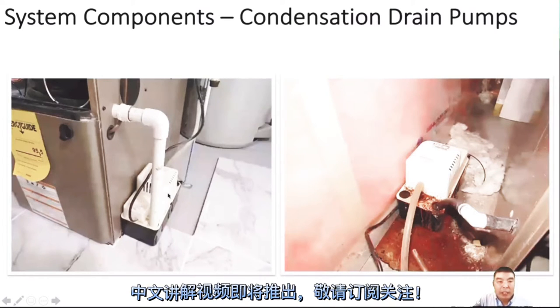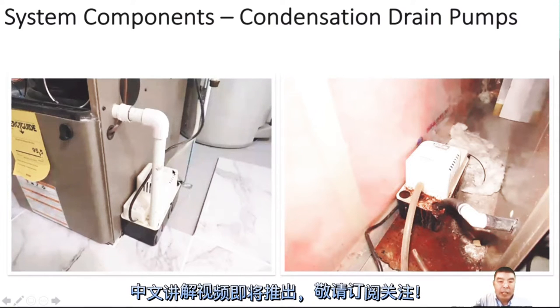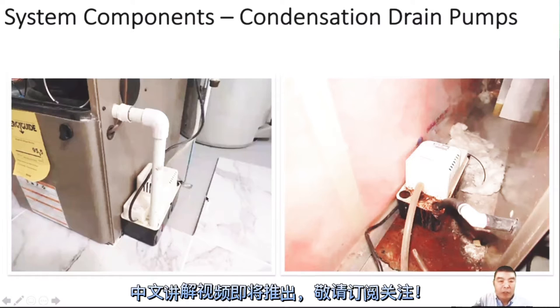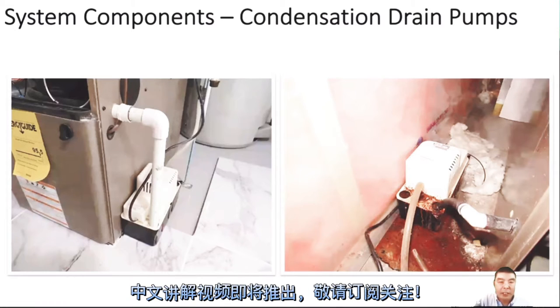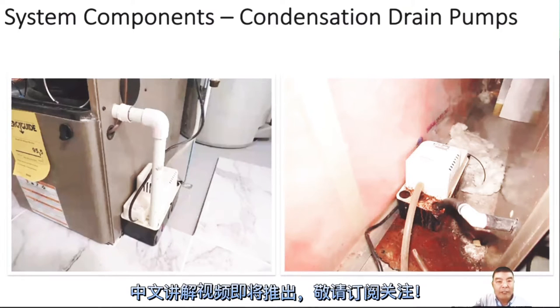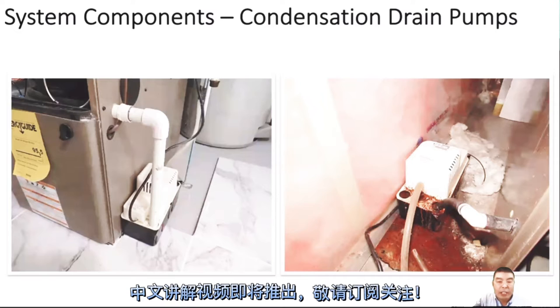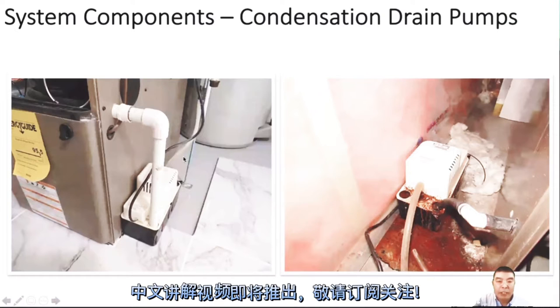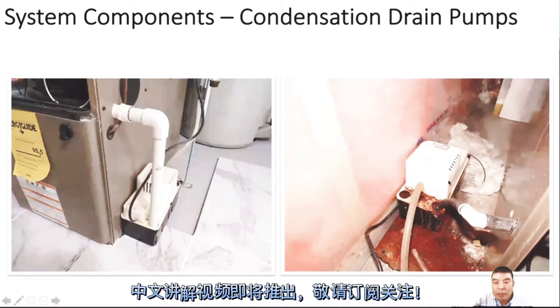This is the condensate drain pump. We normally only use this for the high efficiency furnace when there is no floor drain around the furnace. When we install the high efficiency furnace, the old house maybe never thought about it, so there is no floor drain. So if that's the case, after we install the high efficiency furnace — or even just an A-coil for air conditioning — we still need the condensate pump to pump the water to the closest floor drain or drain system.